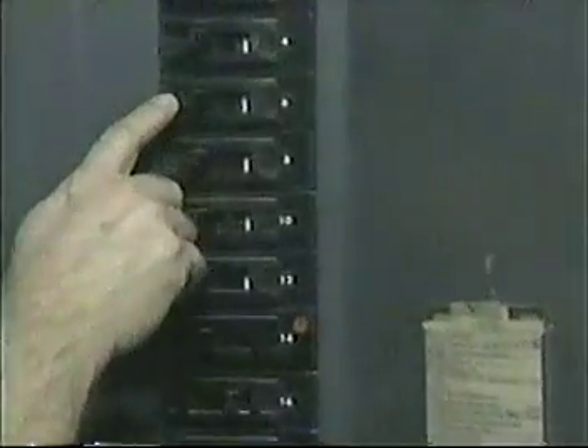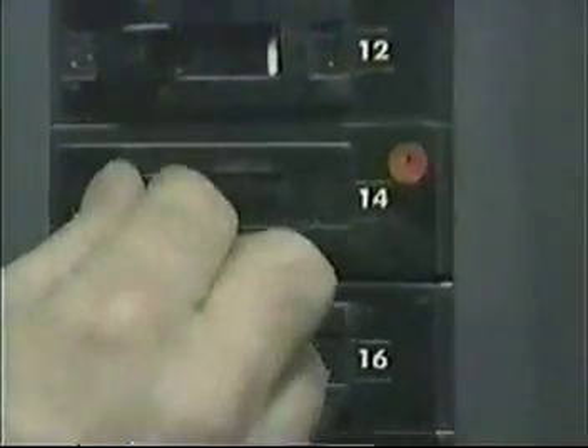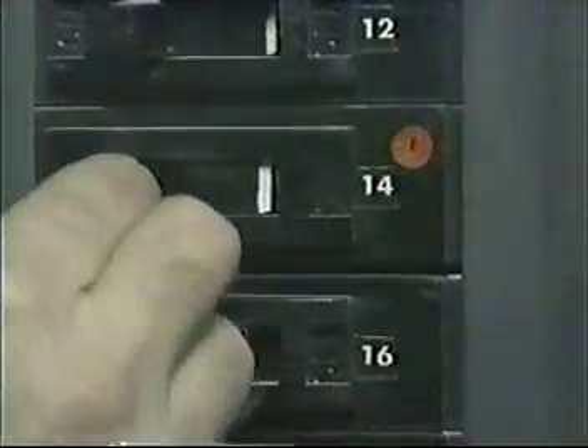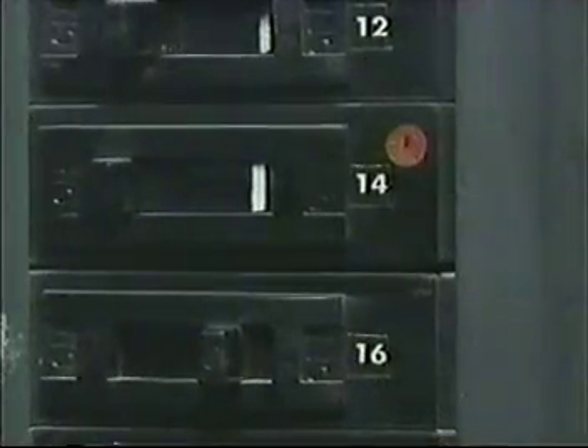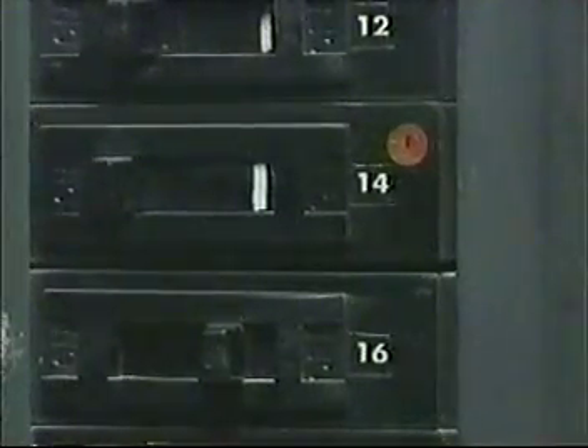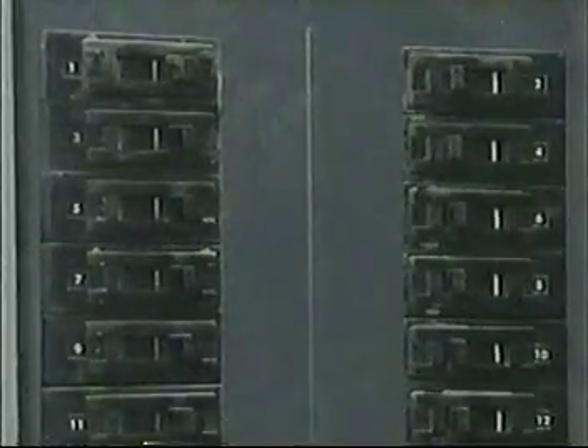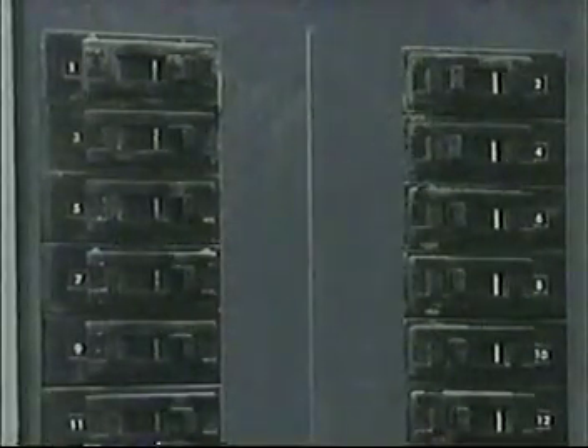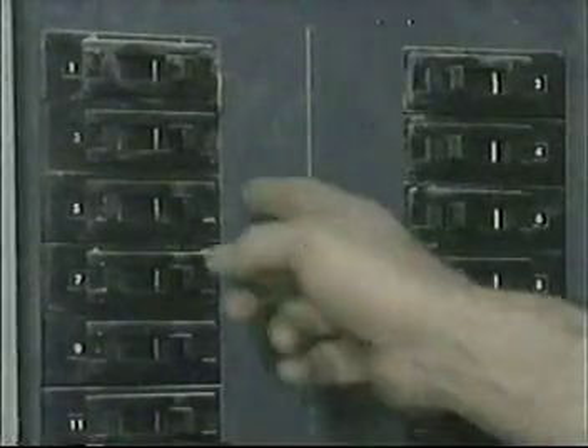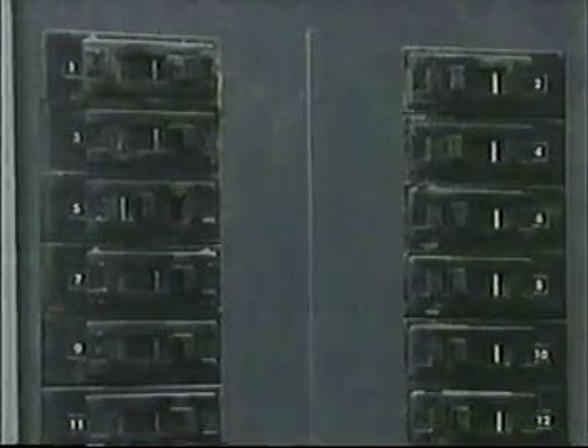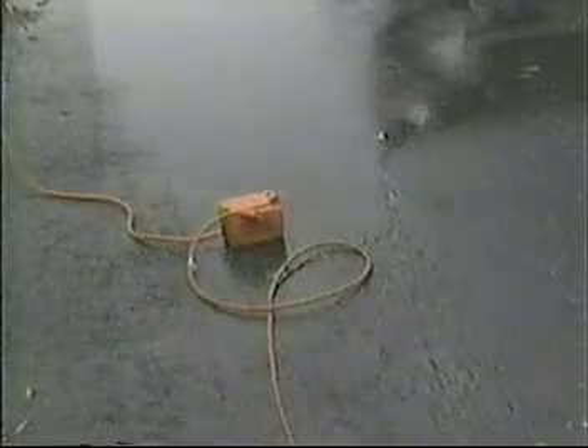Electrical circuit breakers are designed to detect and stop excessive current flows. However, typical breakers do not trip until 15 amperes or more have flowed for 1/4 of a second or longer. This exceeds our body's safety margin by a factor of several hundred. Clearly, circuit breakers cannot be depended upon to provide personal protection, nor are they intended to do so. Their primary purpose is to prevent damage to equipment.